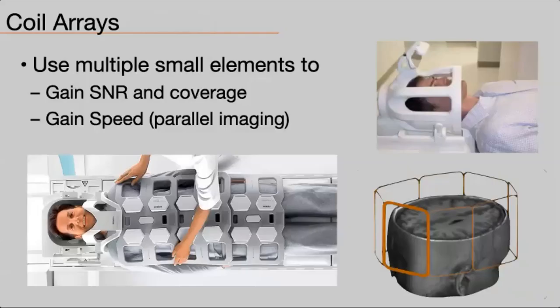To gain both SNR and coverage, arrays of elements must be used. The number of elements has dramatically increased since multiple coils also offer imaging speed through parallel imaging acceleration.